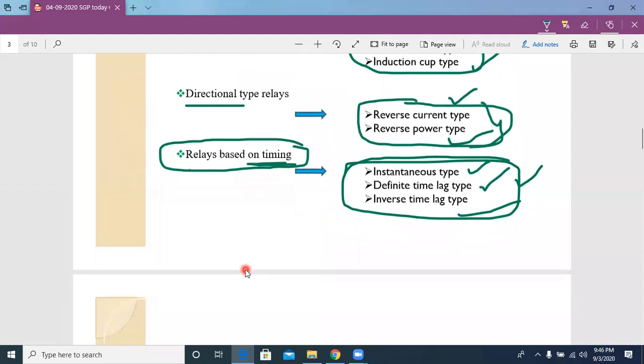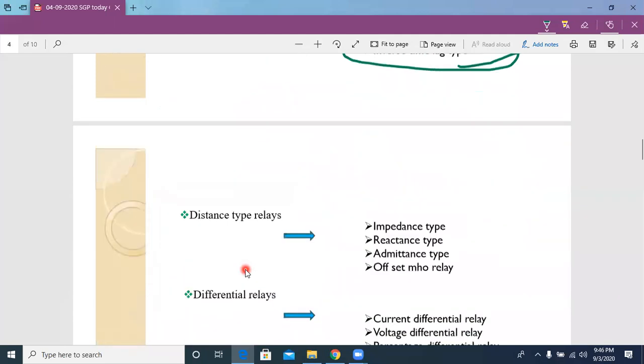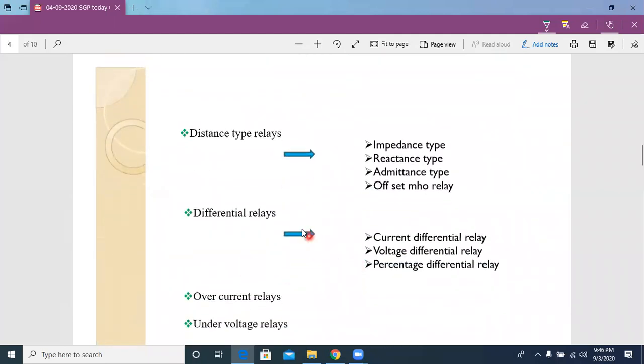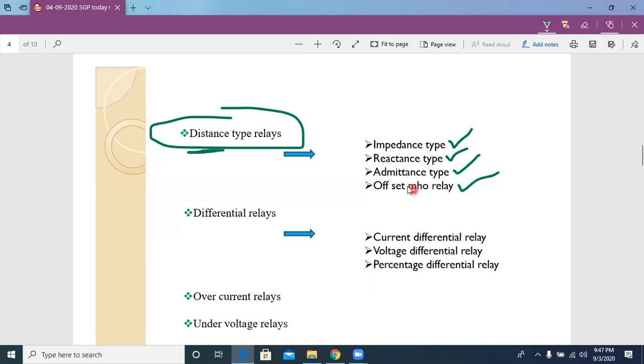Now some more classification about relays. Distance type relays. This one is the logic. Here the logic is distance of activating quantity, and based on this, we have different types of relays like impedance type relays, reactance type relays, admittance type relays, offset mho relays. Here admittance is nothing but mho relays.